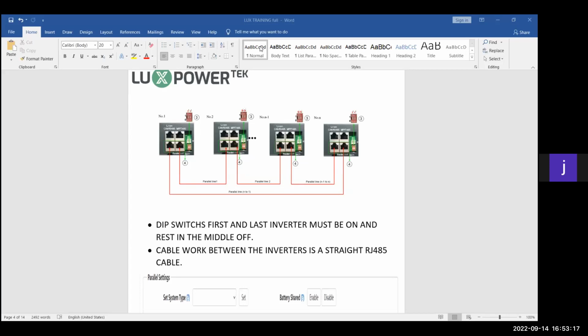Yes, it's exactly the same for single phase and 3-phase systems. And yes, I always use 2 communication cables in parallel. It will work with one alone. If there's only 2 inverters, it can function with one, but I always put in 2 cables, even if it's only 2 units in parallel. So I always use both ports on my inverters. If there's 2 inverters, still 2 cables. As soon as there's a third inverter, you will automatically use all the ports available on your machines. So yes, the configuration stays exactly the same for the 3-phase system.